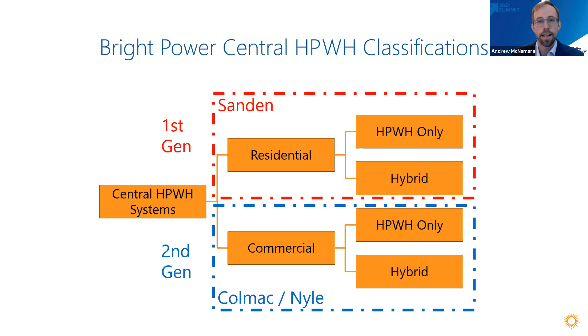This is the heat pump water heater only versus hybrid. Basically, the concept there is we'll share projects which are retrofits in this presentation, where existing boilers were already present on the site. In the hybrid configuration, we leverage a gas boiler, usually the existing gas boiler, as a peaker plant to reduce the required heat pump capacity. Whereas in a heat pump water heater only configuration, there's no natural gas backup, and we have some experience with both. All right, so enough on context.